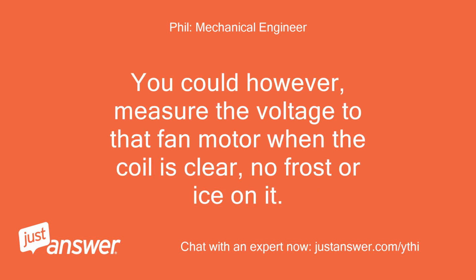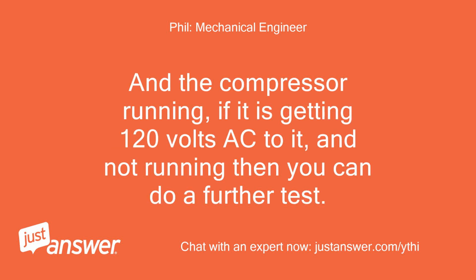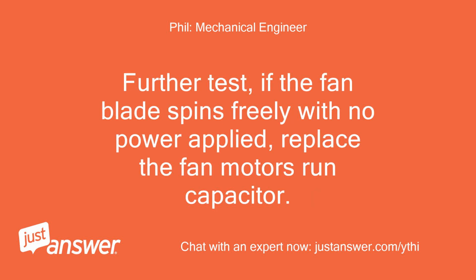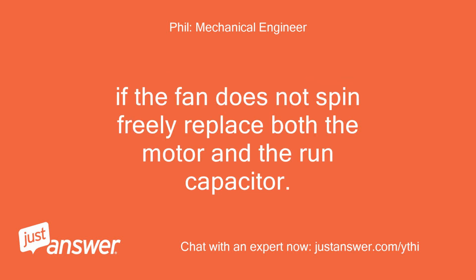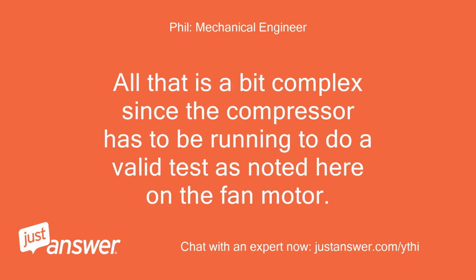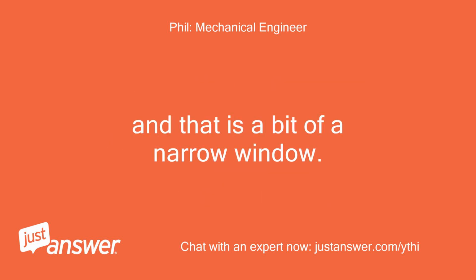You could, however, measure the voltage to that fan motor when the coil is clear, no frost or ice on it, and the compressor running. If it is getting 120 volts AC to it, and not running, then you can do a further test. Further test, if the fan blade spins freely with no power applied, replace the fan motor's run capacitor. If the fan does not spin freely, replace both the motor and the run capacitor. All that is a bit complex since the compressor has to be running to do a valid test as noted here on the fan motor. And that is a bit of a narrow window.